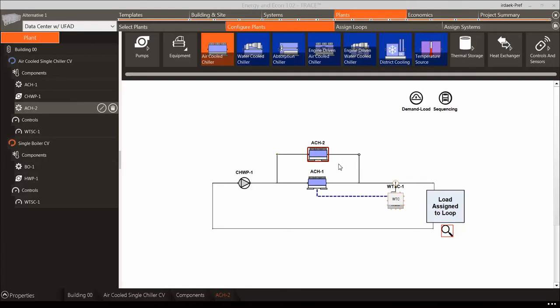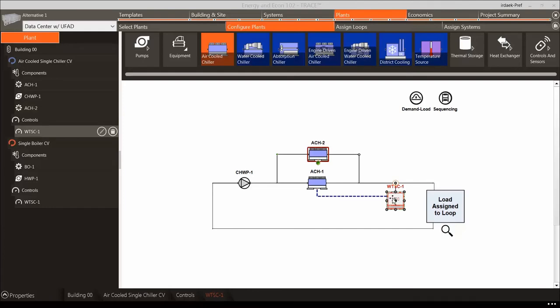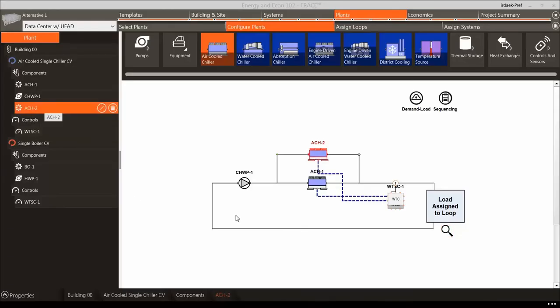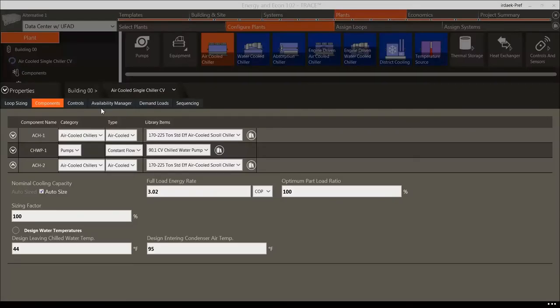In this case, the validation indicates we are missing controls for the chiller we just added. Clicking the magnifying glass for this piece of equipment will highlight the component in the diagram. Scan for Errors is available in Configure Plants, Assign Loops, and Assign Systems. To get rid of the error, close the validation screen, select the controller, and click the green icon to connect the controller to the chiller.